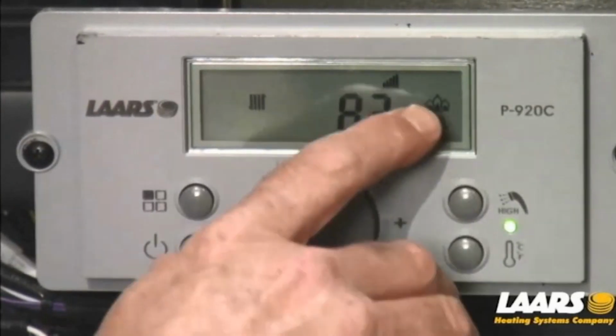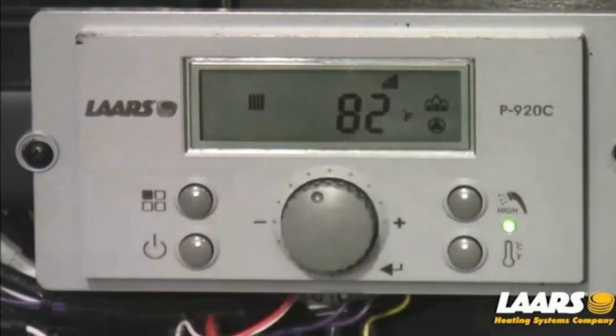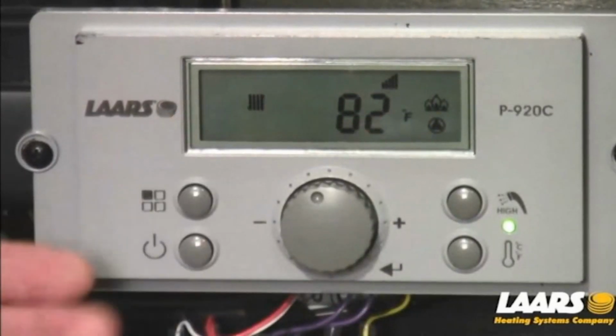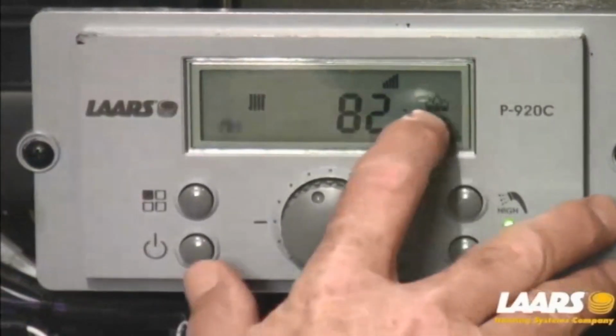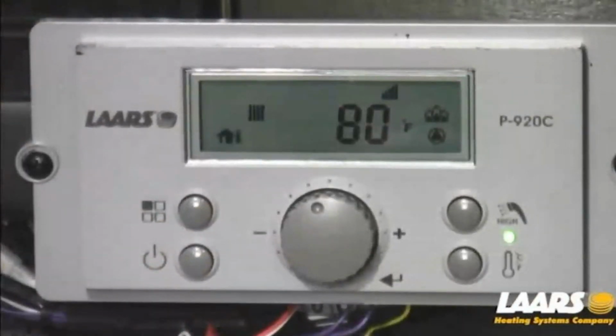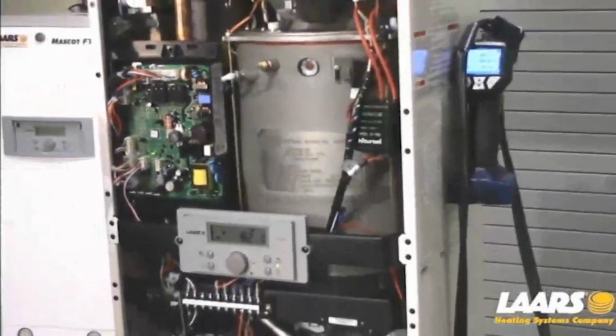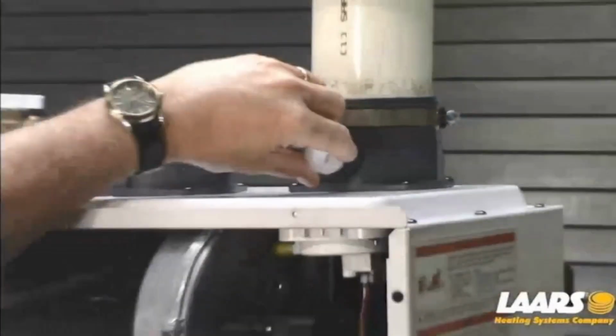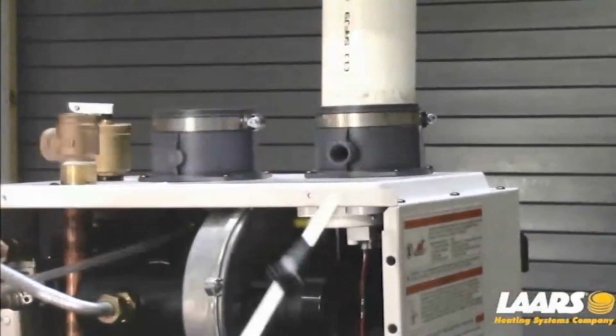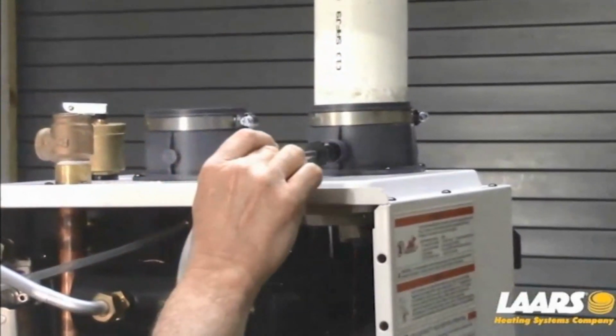All right, so now you can see a flame signal appeared on the screen in a radiator symbol. That tells me we're in central heat mode and we have a flame signal. You can look in your sight window and you'll actually see the flame appear. The very first thing we want to do is set up a combustion analyzer. I'm going to remove the plug from the vent terminal and install the combustion analyzer.